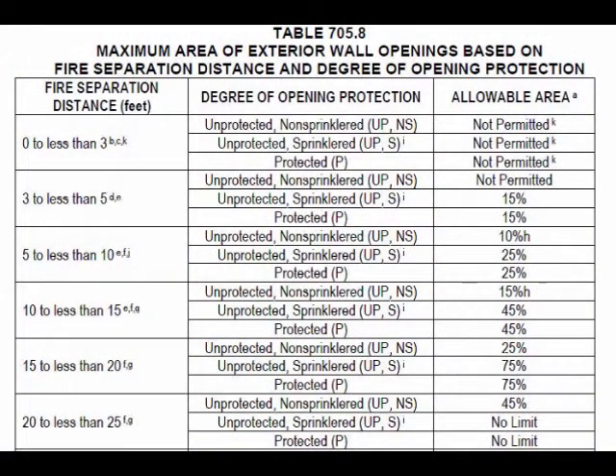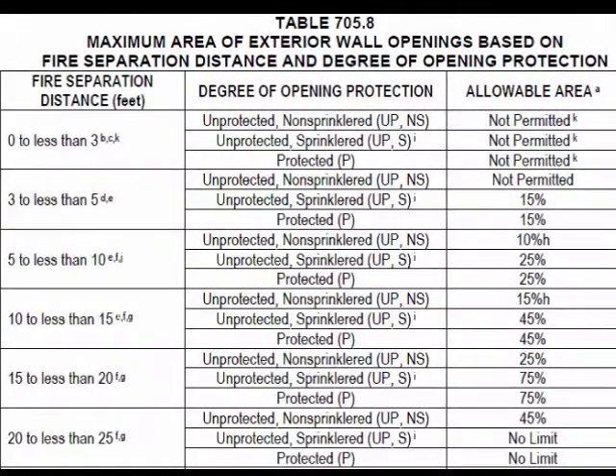Shown here is the applicable portion of Table 705.8, which specifies the maximum area of both protected and unprotected exterior wall openings as a function of fire separation distance. For a non-sprinkled building located with a fire separation distance of 12 feet, up to 15% of the wall on each story is permitted to be unprotected, and up to 45% of the wall is permitted to be a protected opening, protected in accordance with Sections 716.5 and 716.6.